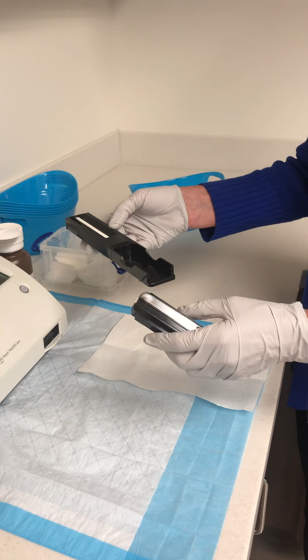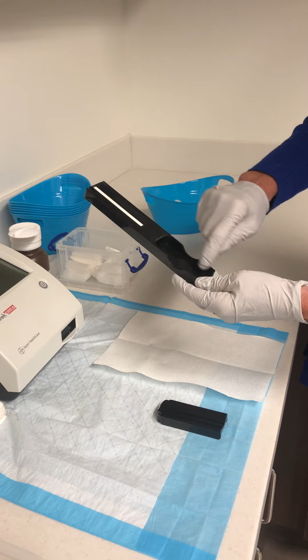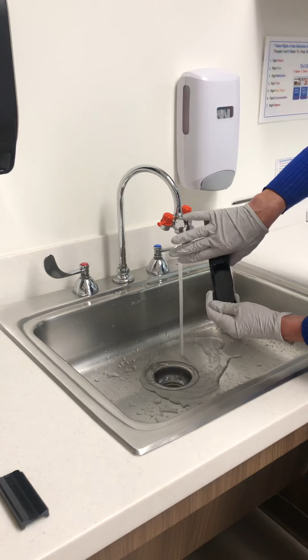So what we would do is get a cotton tip applicator, and if there's any crusted urine here, we would want to remove that. And then we want to rinse both of these with water. Remember, we don't want to get this wet, so what I recommend is holding your hand over it like that, rinsing here, and then you can rinse this little test table. This is after you've cleaned it with a cotton tip applicator. And then we're just going to dry both pieces. Again, I haven't touched that white calibration bar, but I'm drying this area to remove any caked on urine, okay?